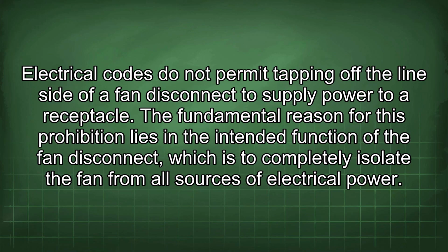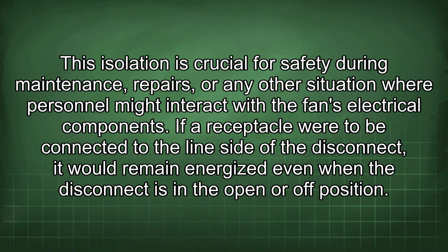Electrical codes do not permit tapping off the line side of a fan disconnect to supply power to a receptacle. The fundamental reason for this prohibition lies in the intended function of the fan disconnect, which is to completely isolate the fan from all sources of electrical power. This isolation is crucial for safety during maintenance, repairs, or any other situation where personnel might interact with the fan's electrical components. If a receptacle were to be connected to the line side of the disconnect, it would remain energized even when the disconnect is in the open or off position.